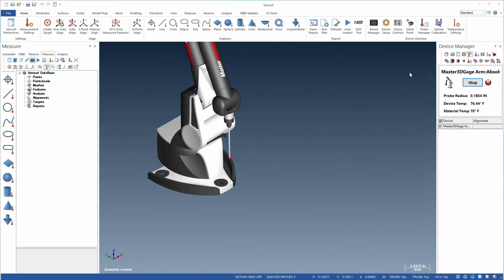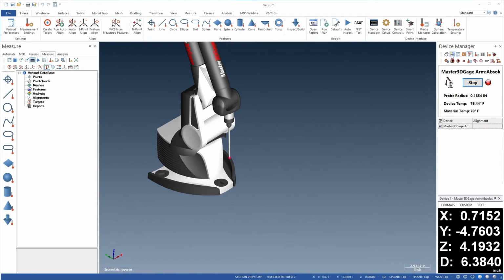Prior to starting any measurement project, it's important to check the performance of the Master3DGage to ensure its accuracy. In this video, we'll evaluate the device using a few quick checks that can be run following setup using only a simple probe target. With the Master3DGage running and secured to the inspection table, we'll use the DRO button to open a new digital readout of the probe coordinates.